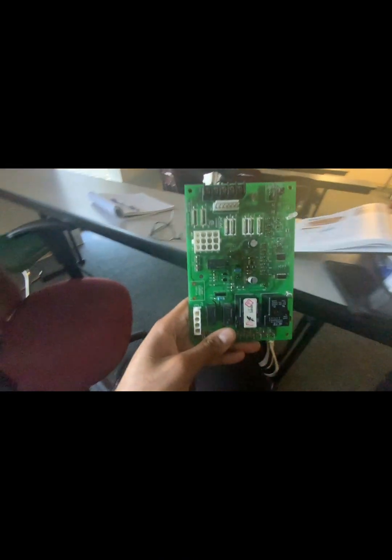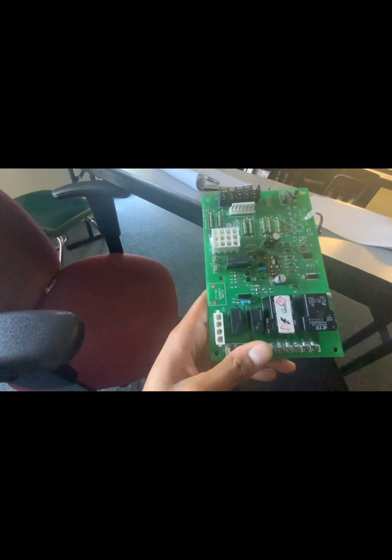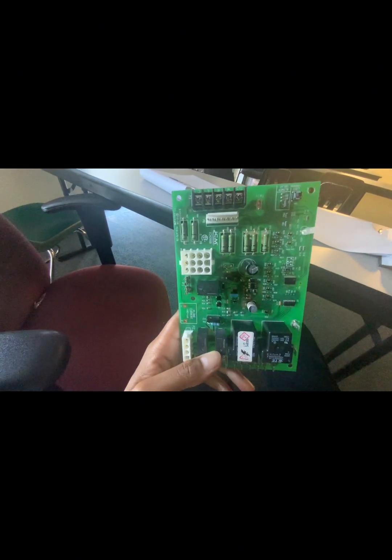And what else? How does a relay work? Did it talk about potential relays as well? That's more on refrigeration, most of yours would be fan relays. Cause you asked about a relay, didn't you? Potential, that's the dangerous lab. Yeah, we talked about potential relays. Potential relays are used on larger equipment and on refrigeration equipment, like coolers and freezers, on those type of compressors.